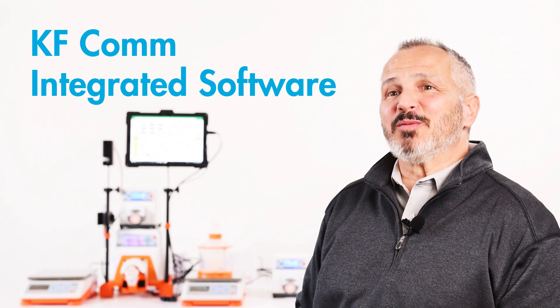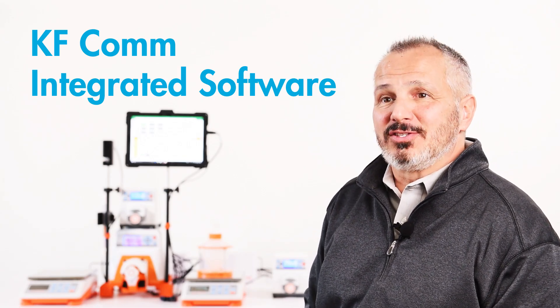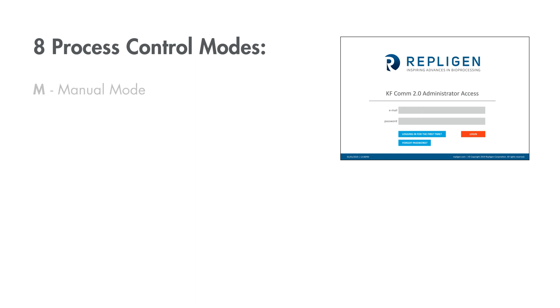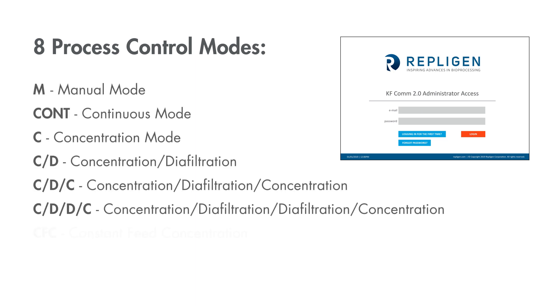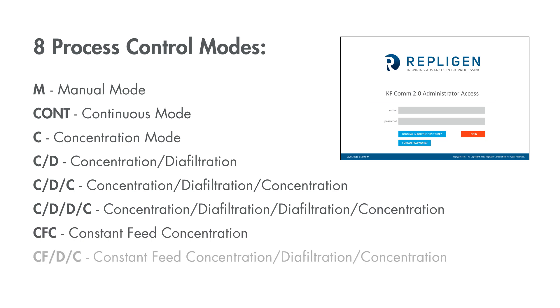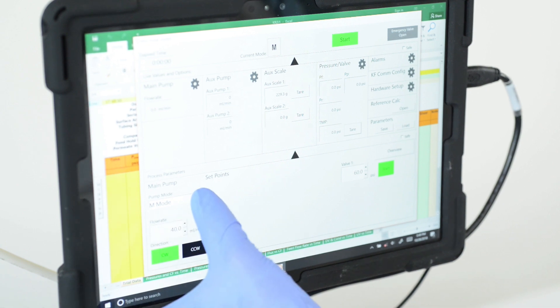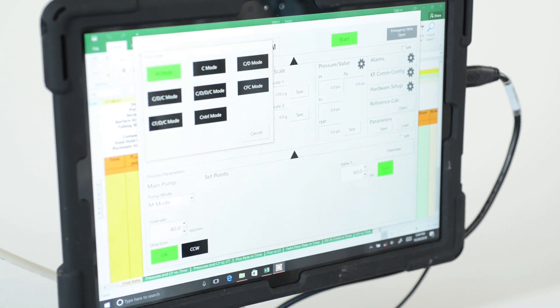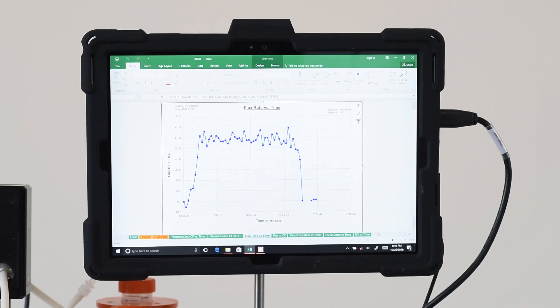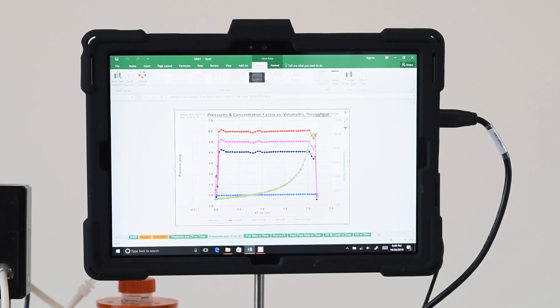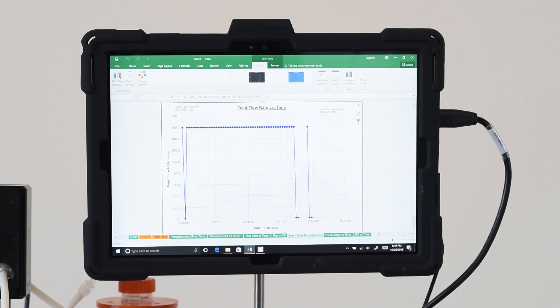KF Comm software comes with eight pre-configured methods, including manual mode. Why is that important? The methods provide reproducible use of the system — you can virtually reproduce the process over and over again. The method profile can be saved and simply recalled to quickly set up and perform an experiment. The KF Comm software gives real-time feedback and recording as minimal as every two seconds, with real-time graphs of the operation.